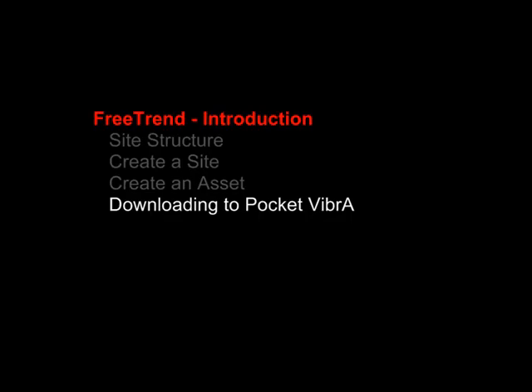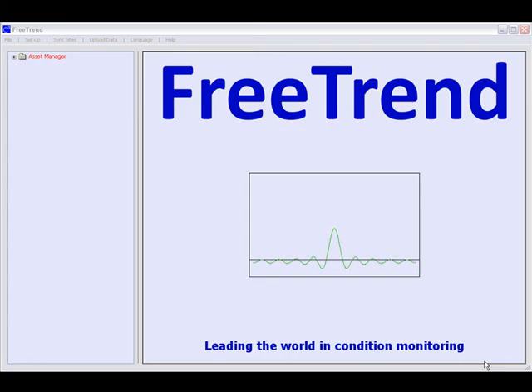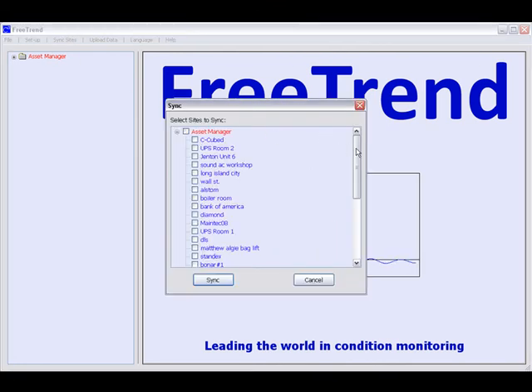My final task is now to download the new site and assets to the Pocket Vibra Pro handheld. Before starting downloading, it's important to make sure that the Pocket Vibra handheld is connected to the PC and that ActiveSync is running and showing as connected. To synchronize sites to the handheld Pocket Vibra unit, simply click on the Sync Sites button at the top of the screen. Then check any of the sites that you wish to synchronize.